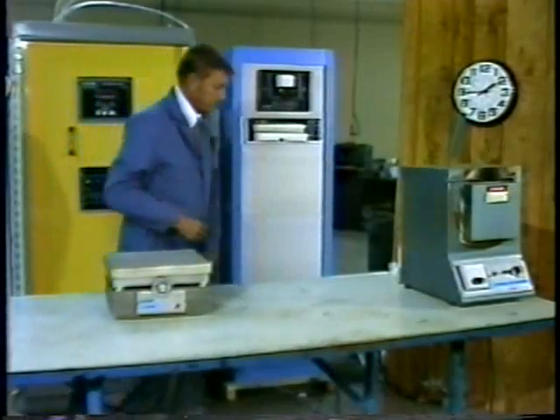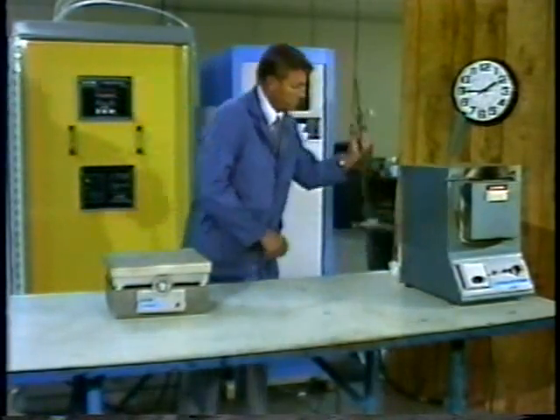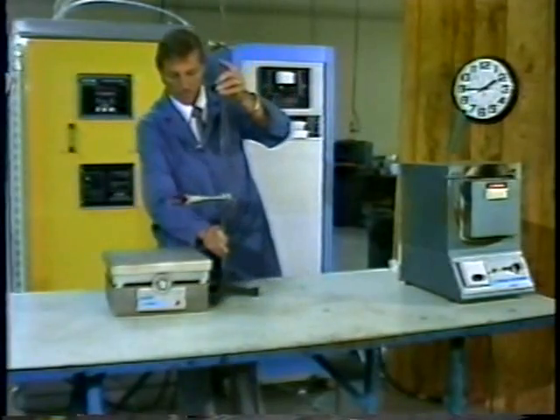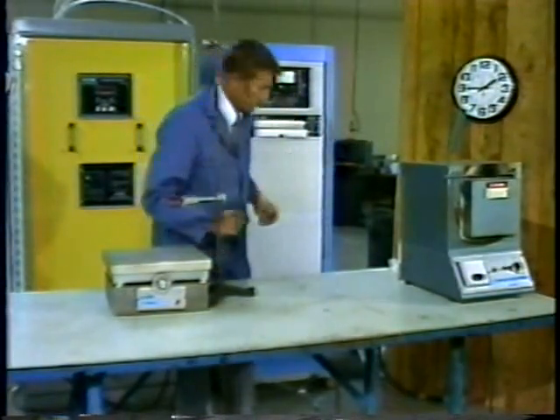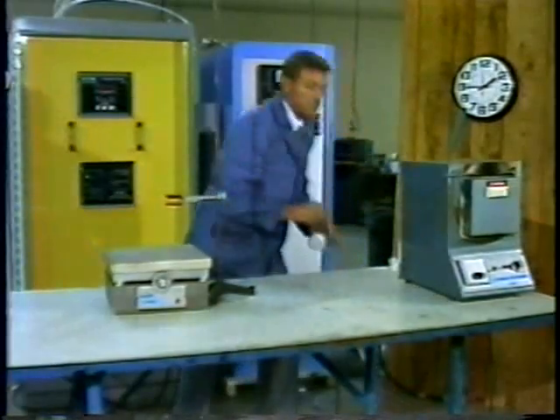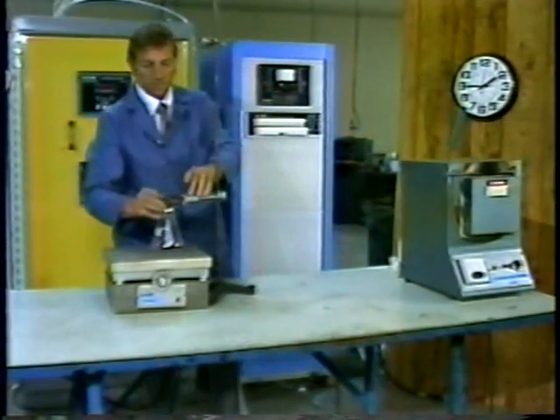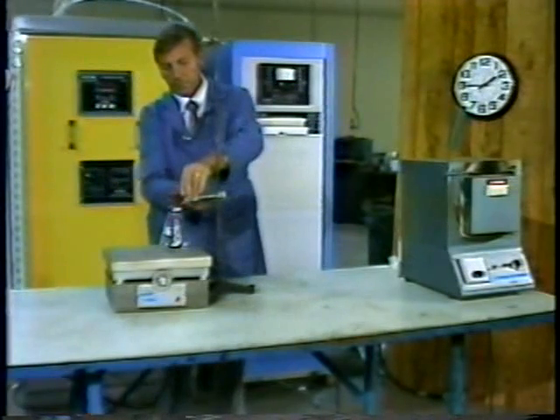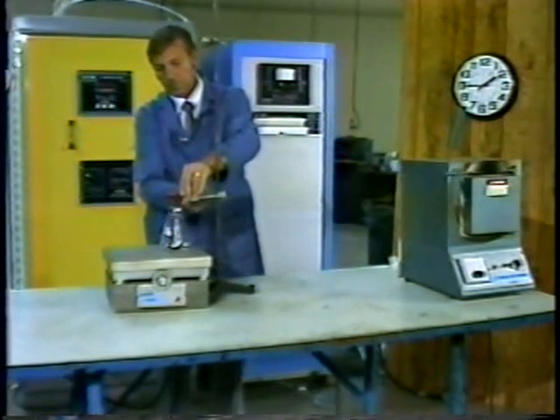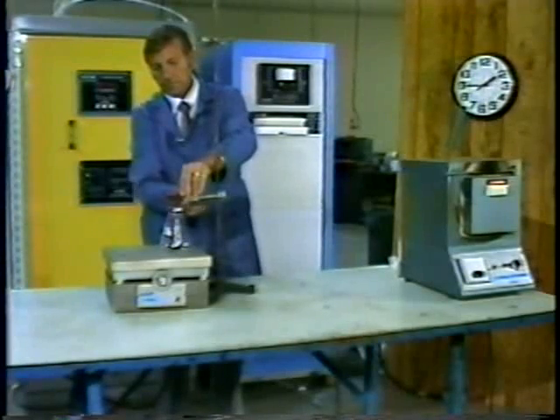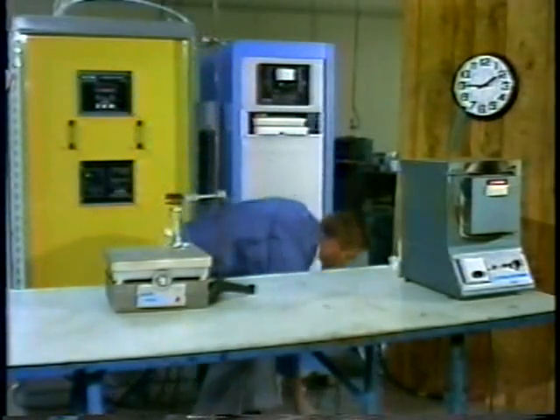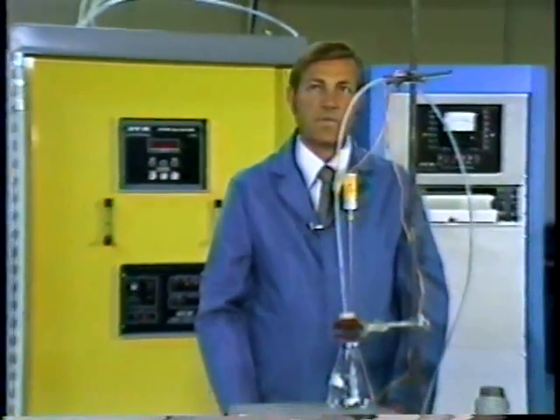As we already know, the oxidation process releases gases and particulates as well as the energy that thermocouples attempt to measure. Both carbon dioxide, CO2, and carbon monoxide, CO, are products of coal oxidation. Of these two, carbon monoxide is proven to be the most sensitive indicator of oxidation. This knowledge provides the key to the KVB coal fire protection system.